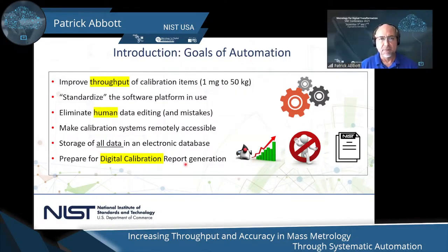Well, we're in mass calibration, and I'll talk a little bit about that, but not too much. But first of all, what we want to do, and I've highlighted very important things in yellow, is to improve throughput of calibration items. And when I talk about items, just to give you some tangible representation, it's something between 1 milligram and a 50 kilogram object that people use as mass standards. We have a much broader range that we calibrate, but for now, in our automation, we do 1 milligram through 50 kilograms, so keep that in mind.